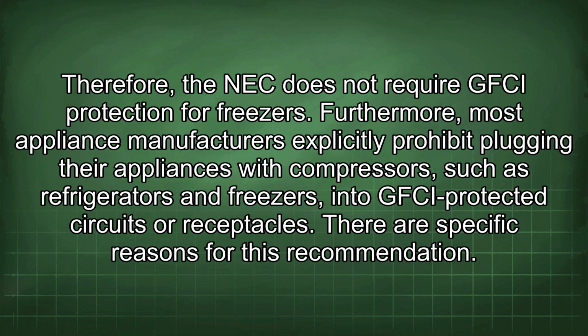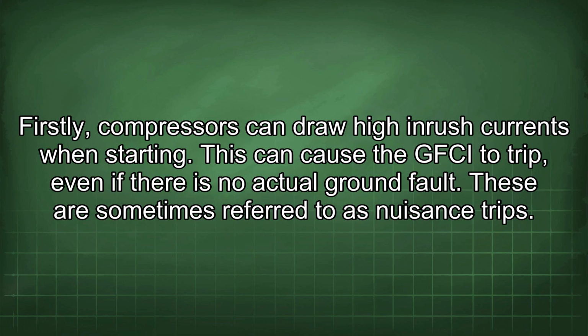Furthermore, most appliance manufacturers explicitly prohibit plugging their appliances with compressors, such as refrigerators and freezers, into GFCI protected circuits or receptacles. There are specific reasons for this recommendation. Firstly, compressors can draw high inrush currents when starting. This can cause the GFCI to trip, even if there is no actual ground fault. These are sometimes referred to as nuisance trips.